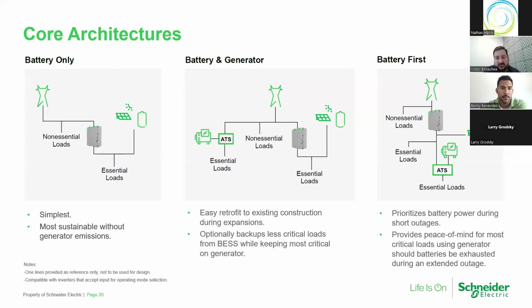There are also applications where battery and generator coexist. As I mentioned earlier, these battery energy storage systems have a finite duration of power. So if the outage prolongs longer than 6 hours, you have some life safety equipment, it's very important to at least have that on generator or backup power. So here in that middle diagram, we have an ATS that's connected to a generator feeding essential loads. And then we also have the SourcePack device on the right feeding essential loads, which again, when we're working with a consultant or a contractor and user on the design, we want to understand the load prioritization: which loads have criticality, which ones must be on at all times, and which ones after a prolonged outage can accept the power outage for X amount of time before utilities restore.